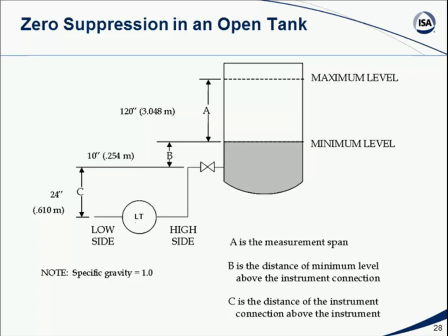So I've got to correct for that. That's my 0 value. So in other words, even when the tank's essentially empty, I'm still measuring 24 inches of fluid in the tank, so I've got to correct for that. I've got to subtract that off, or zero the calculation.